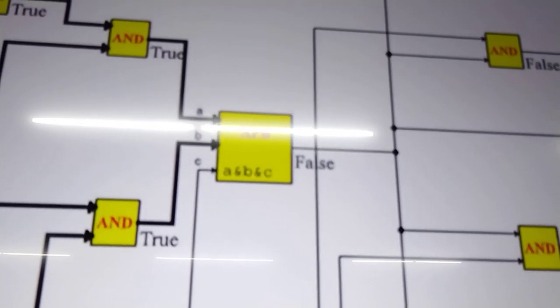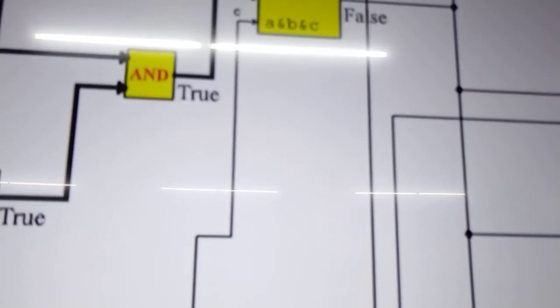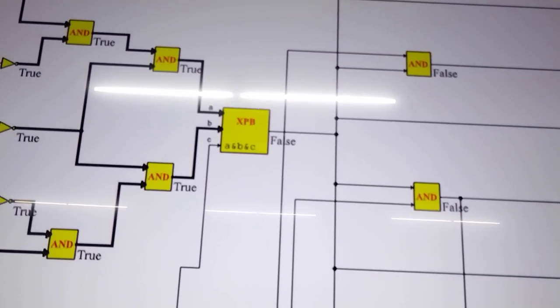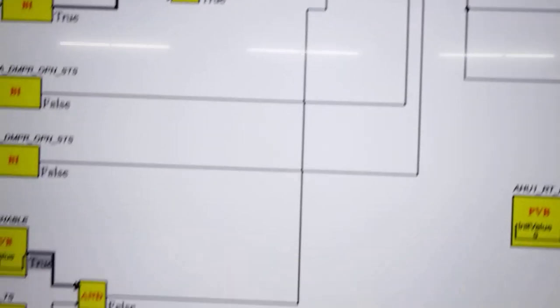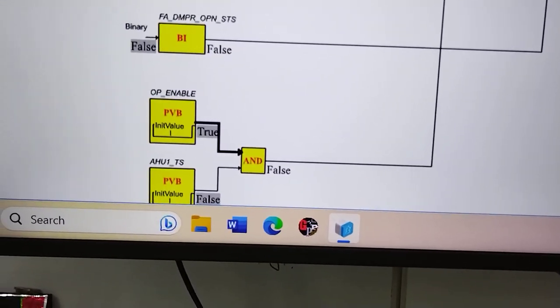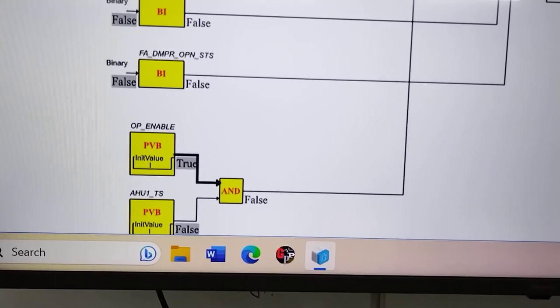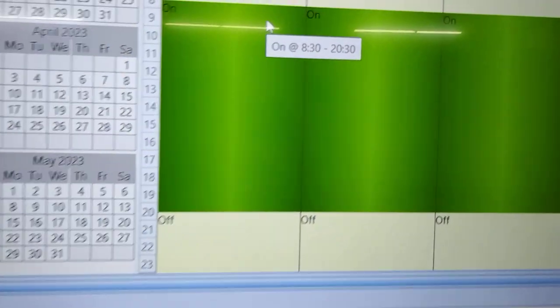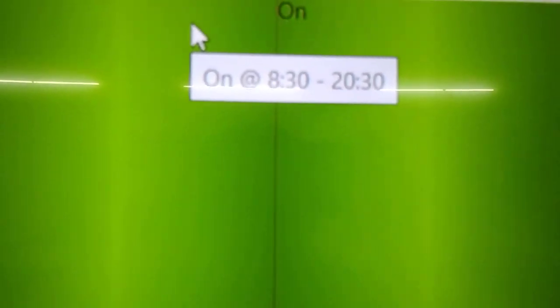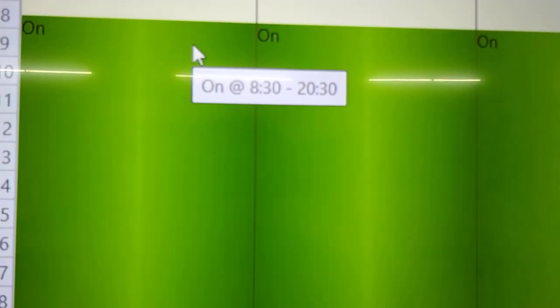This expression block output is binary — it's actually a combination of an AND gate. If A and B and C are all true, it will give an output of 1. But since we have one input which is false, the truth table of an AND gate requires all inputs to be 1 before it gives an output of 1. So we need to make this AHU time schedule true. Let me show you why it is false. What I have here is the time schedule.